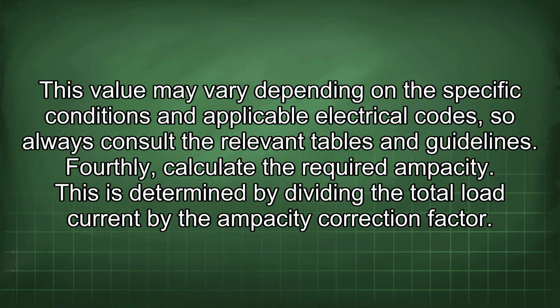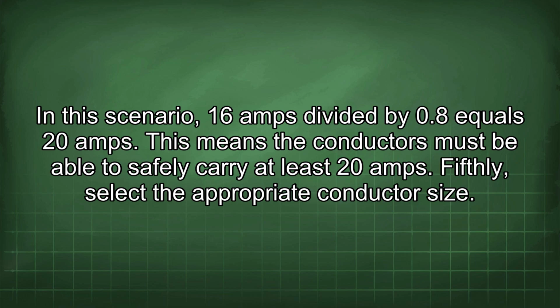Fourthly, calculate the required ampacity. This is determined by dividing the total load current by the ampacity correction factor. In this scenario, 16 amps divided by 0.8 equals 20 amps. This means the conductors must be able to safely carry at least 20 amps.